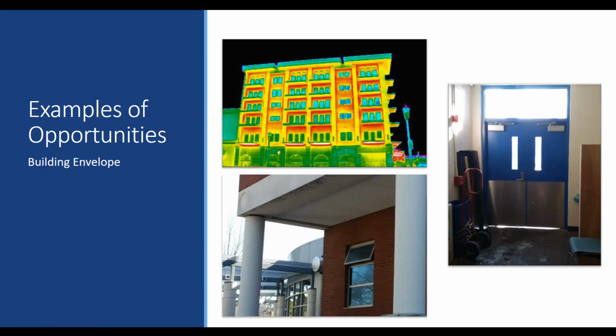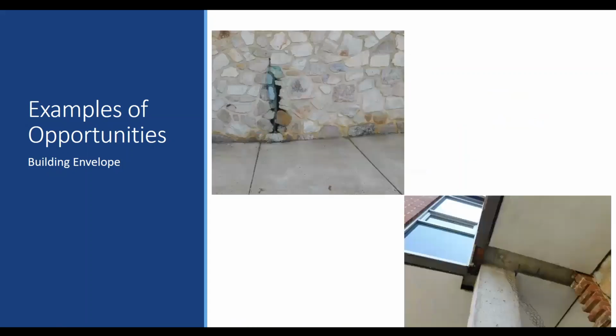After completing the investigation of the building's envelope, it would be reasonable to review the HVAC system and its controls. Also in the right photo reveals a lot of air infiltration. Anytime you can see natural daylight under doorways or windows, you have airflow. Other envelope examples include unsealed penetrations. Are there unsealed penetrations in your building? Look for infiltration around seams or pipe penetrations in your building envelope. Improperly sealed holes will allow for an increase of infiltration into the building.